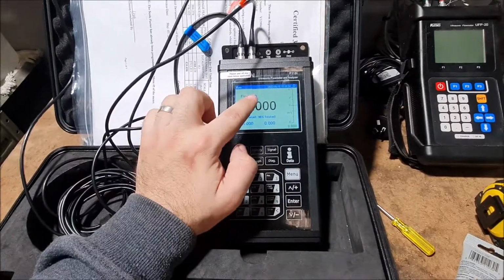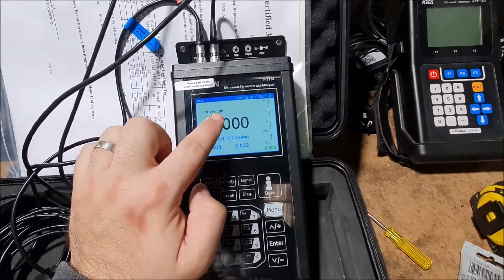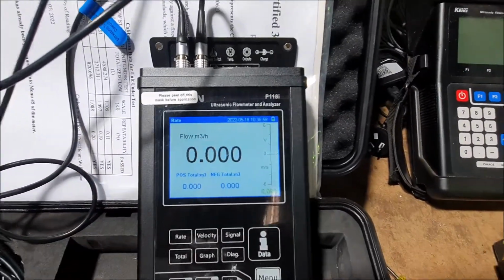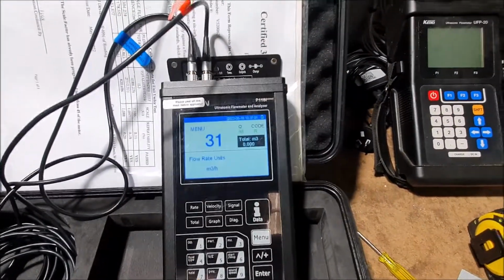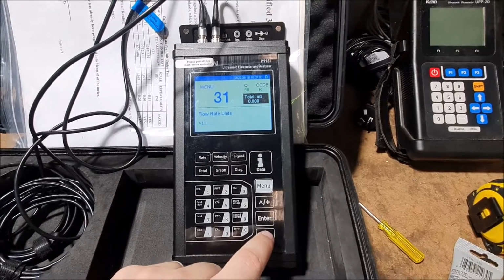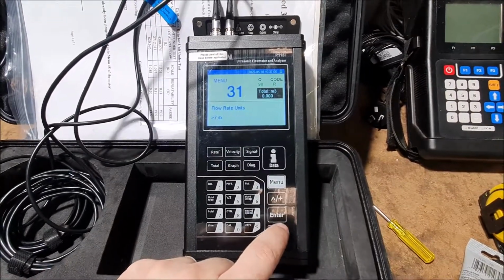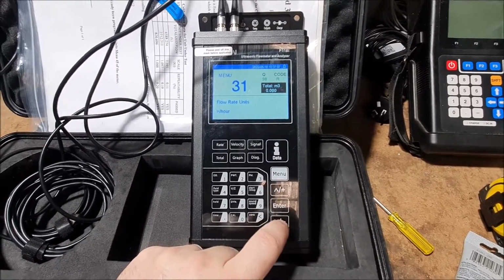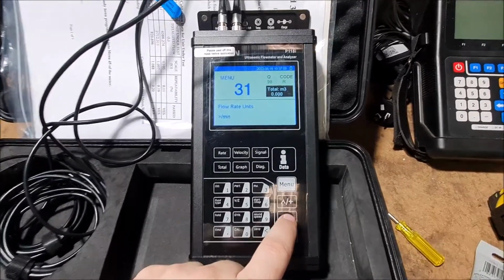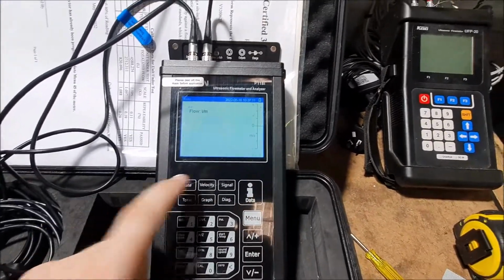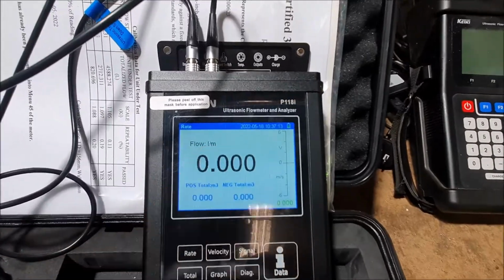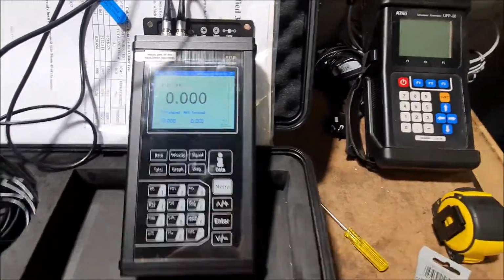One other thing I want to change is my units. At the moment I've got M3H. If I go to menu 31, I can change this, and you can change that to various units. I'm just going to go with liters, and then I'm going to make it a minute, so liters a minute, and I'll see that up here on my rate screen.